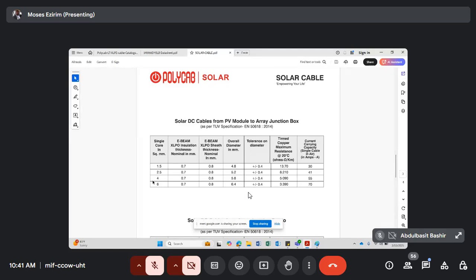So I can conveniently use 4 mm cable. What I can conveniently do to know if you are going to use 4 mm is check voltage drop. If the distance is more, you consider voltage drop, and if it is not within range, then...